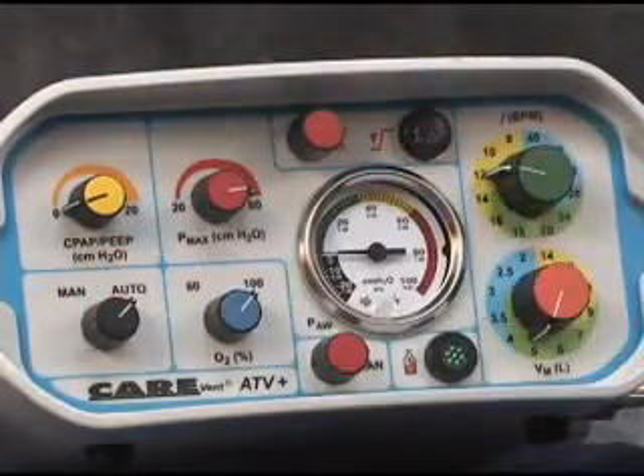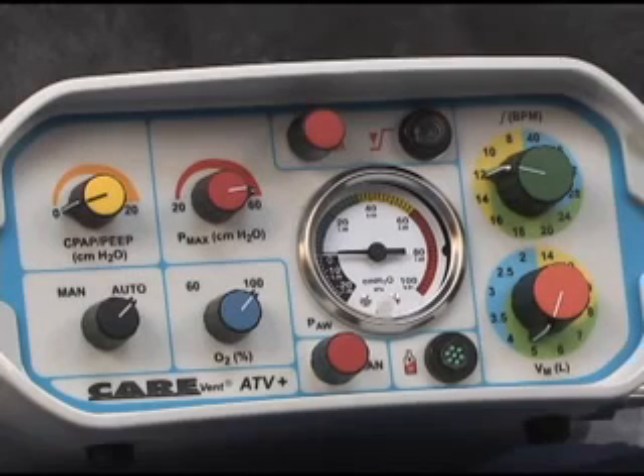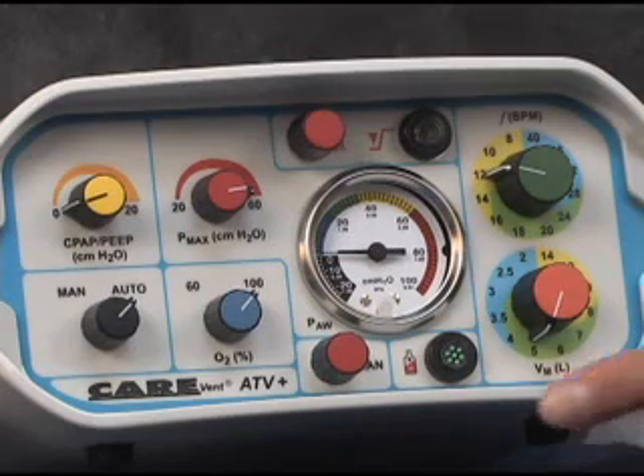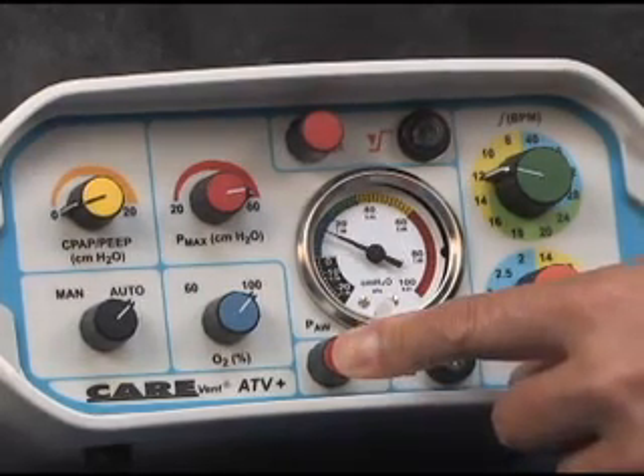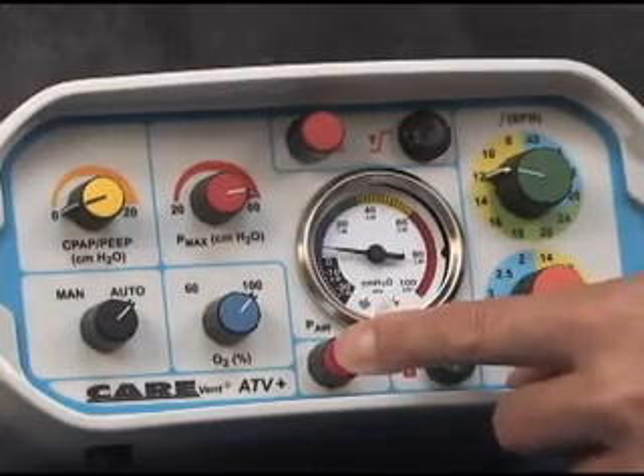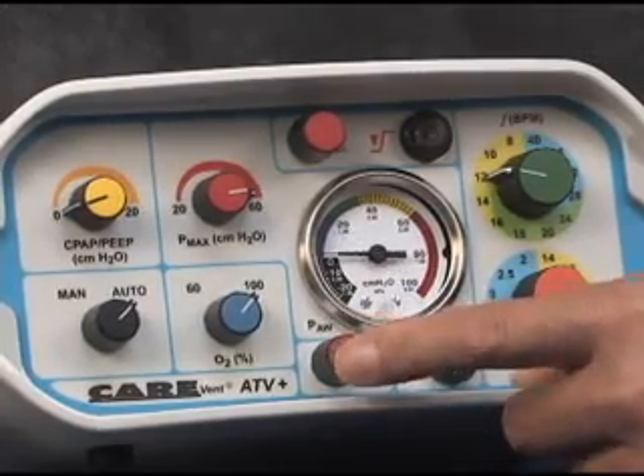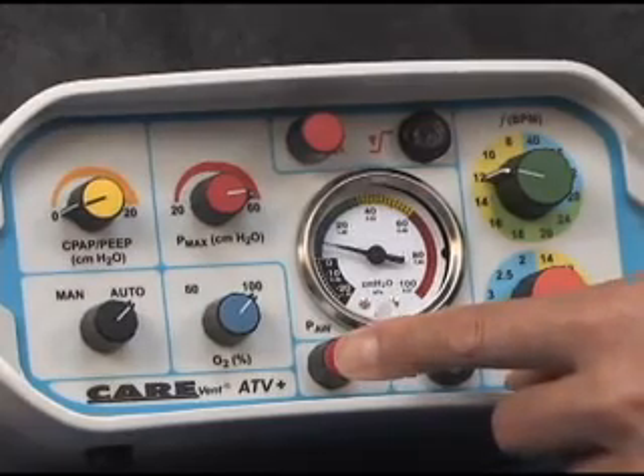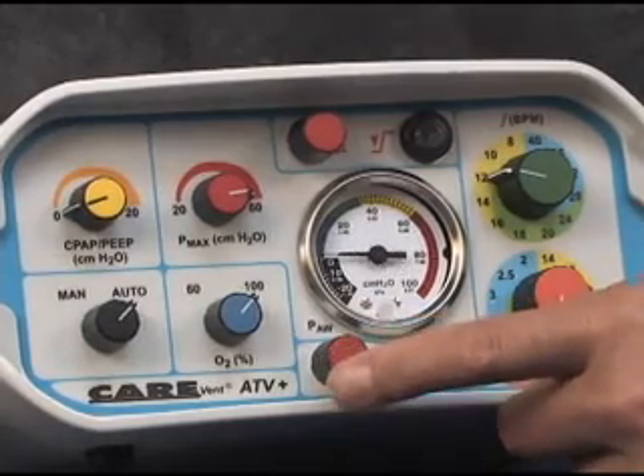Turning the manual automatic control to the auto position will allow the ventilator to commence automatic cycling at the selected frequency and minute volume. Should the rescuer wish to manually ventilate the patient, depression of the manual ventilation button will override the automatic cycling, causing it to cease. The rescuer can then ventilate the patient at their own rate and volume. However, the flow rate of gas will remain equivalent to the selected minute volume setting.